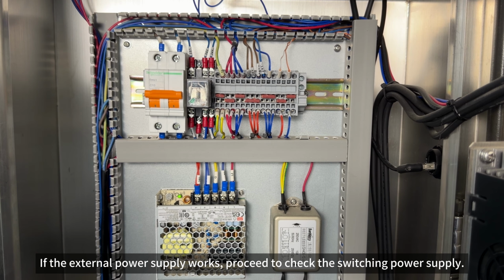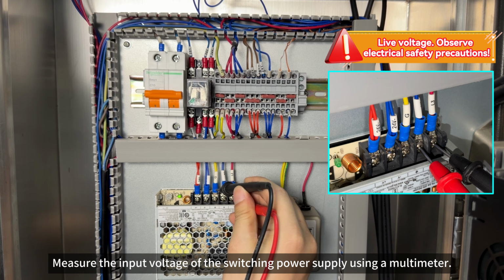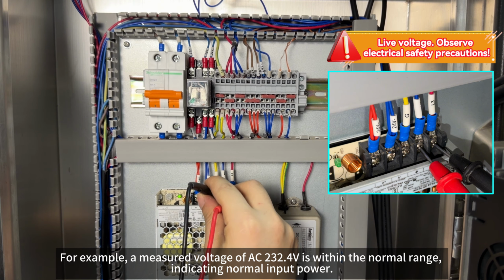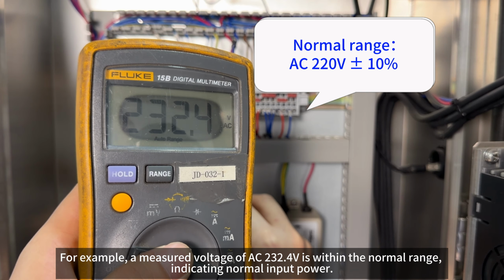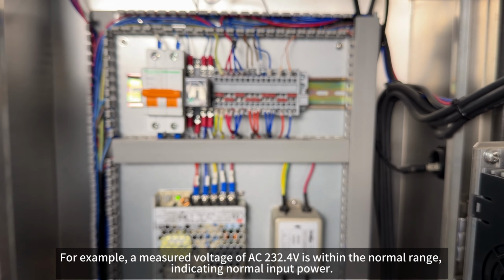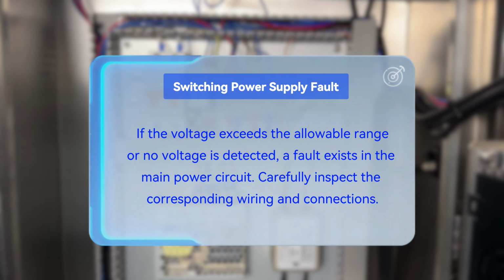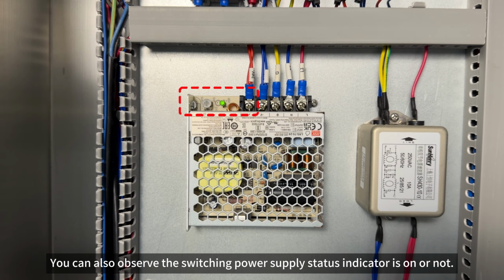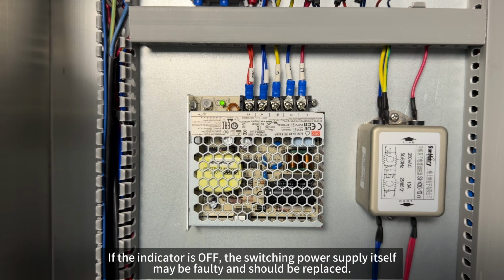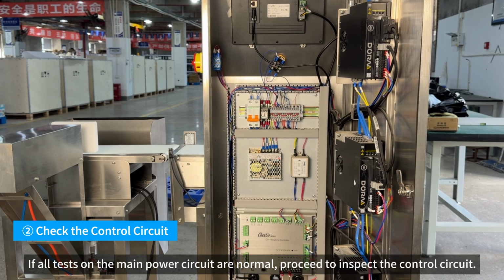If the external power supply works, proceed to check the switching power supply. Measure the input voltage of the switching power supply using a multimeter. For example, a measured voltage of AC 232.4 volts is within the normal range, indicating normal input power. If the voltage exceeds the allowable range or no voltage is detected, a fault exists in the main power circuit. Carefully inspect the corresponding wiring and connections. You can also observe whether the switching power supply status indicator is on or not. If the indicator is off, the switching power supply itself may be faulty and should be replaced. If all tests on the main power circuit are normal, proceed to inspect the control circuit.